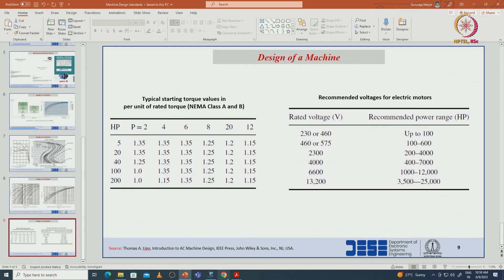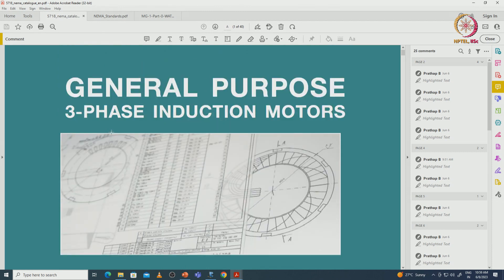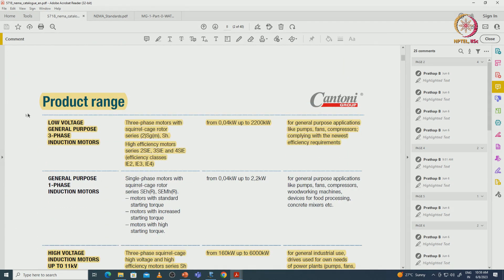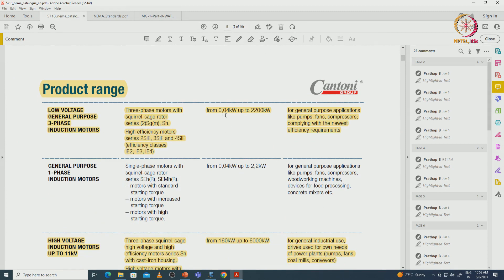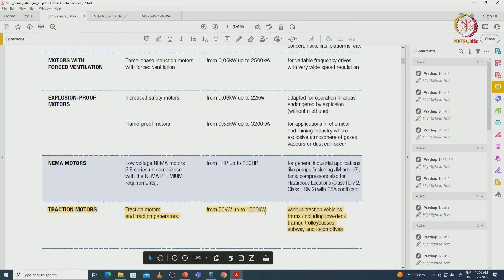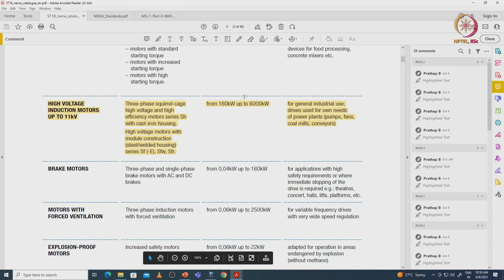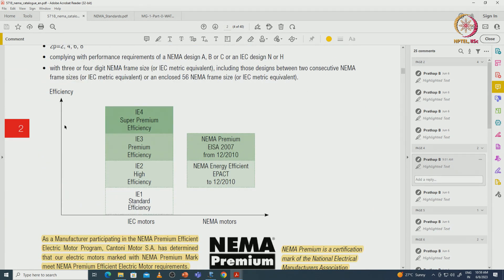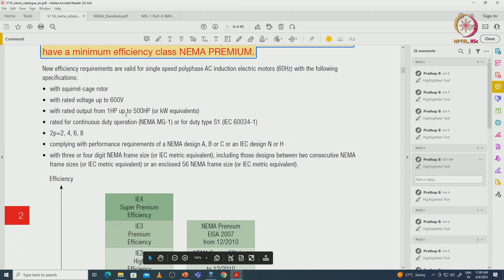Looking at the standards for three-phase induction machines from a product data sheet: low voltage general purpose induction machines range from 0.04 kilowatt to 2200 kilowatt; high voltage machines go up to 11 kV; and traction motors up to 1500 kilowatt. The efficiency class is defined with respect to IEC standards (IEC 60034) and NEMA standards (MG1) for a given voltage, with power ratings up to 500 HP and pole counts of 2, 4, 6, etc.